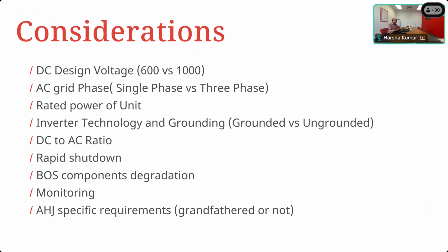on the DC side of the PV array, preferably under wet conditions, because merely having failed insulation doesn't mean you're going to have a leak to ground, because air does not conduct electricity. So you need to be well aware and adept at making sure that you perform an insulation test on the PV array using a megger or a megohm meter to make sure that there are no leaks to ground before you hook up an inverter to an older PV array.